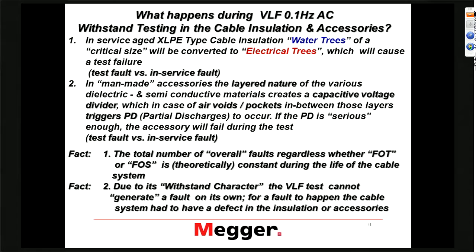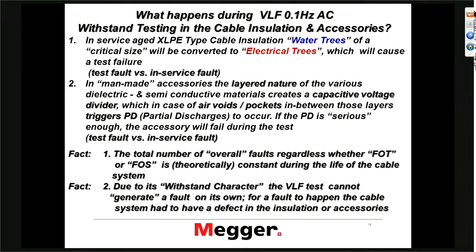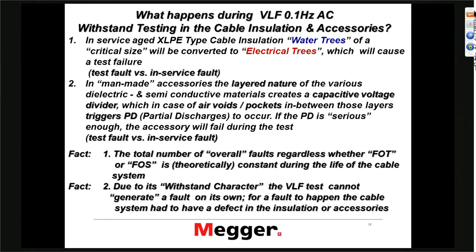Water trees that have reached a critical size will be converted by the high electrical field from the VLF test to electrical trees. These trees then grow very rapidly and will fail. This is basically flushing the weak spots out during the VLF test. The time you use — how long you do the test — is a little bit of a compromise between how many test failures you want to see versus in-service failures.